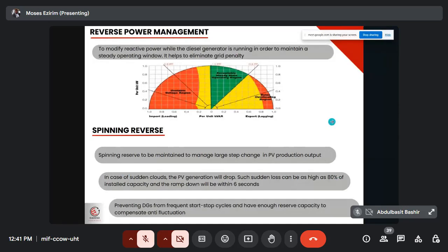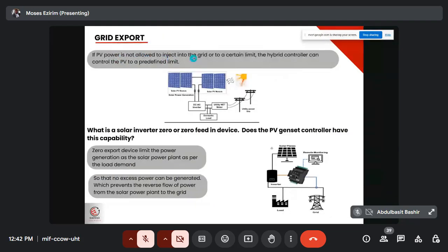Now remember, once you connect your controller to your generator, the controller automatically has control of the generator. All right, automatically everything that has to do with operating it. So now let's move on. This is grid export. If PV power is not allowed to inject into the grid, or there is another limit, like in Nigeria here, the hybrid controller can control the PV to predefined limits. That's what we are talking about.